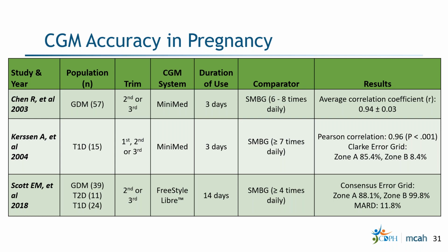So, I'm sharing with you, keep in mind, some of this is older data, but we have this first study, Chen and colleagues, all the way back from 2003 with a MiniMed, which is Medtronic. It was an older version though, and they compared 3 days of use to SMBG that was done 6 to 8 times daily, showing that the correlation coefficient was 0.94, and the closer it is to 1 indicates the better accuracy. So that was shown to be pretty accurate.